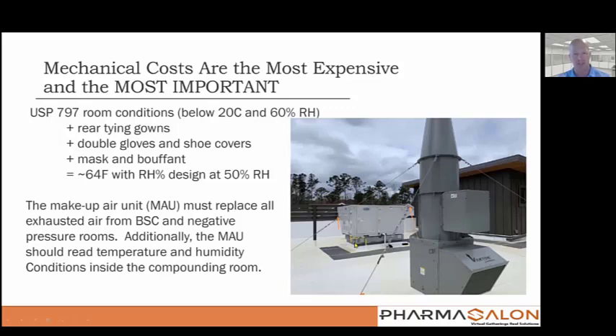There's nothing about your existing commercial DX equipment, that's a recirculating piece of equipment, that was ever meant to do externally venting. It just doesn't exist. So this is where the brunt of the money goes right here when you put this up on your roof or outside on the curb, and there's always other things happening with every building. But this is the unintended consequence of USP 800. So the makeup air unit right here must replace all the exhausted air from the biological safety cabinet, which is connected to this, right? And it should also read temperature and humidity.